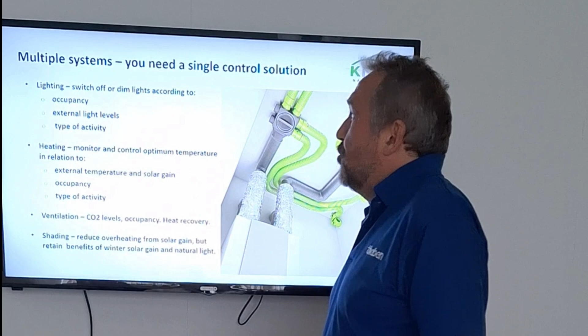Lighting: switch off or dim lights according to occupancy, external light levels, and the type of activity. Heating: monitor and control optimum temperature in relation to external temperature and solar gain. You don't want to be heating a room when there's no one in it, and you need to consider the type of activity happening in that room. Multiple people in a room will increase CO2 levels, and you need to control those CO2 levels with ventilation, but you don't want the ventilation running all the time and throwing away potentially useful heat.